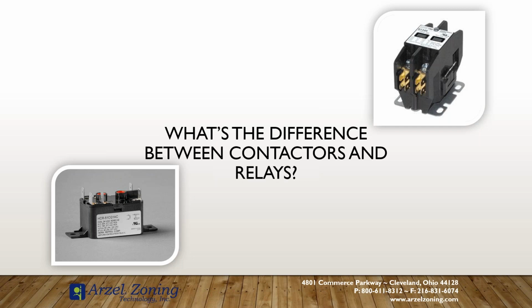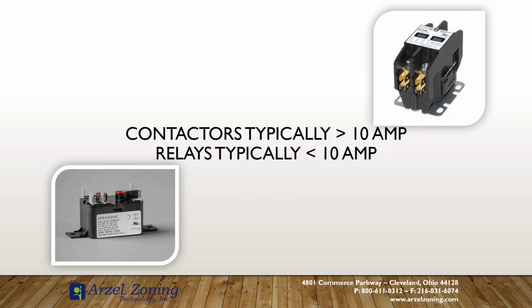So for what we do in the HVAC industry, the only difference really between a contactor and a relay is the amount of current it's designed to handle. Yep, you got that, Robert. Good. So the contactor is typically designed for greater than 10 amps. The relay is typically designed for less than 10 amps. So when we're looking at the contactor and relay, the difference is really just on the amount of current the device is designed to handle.